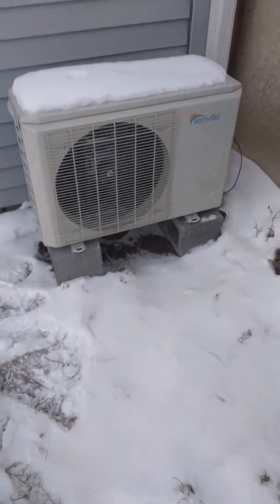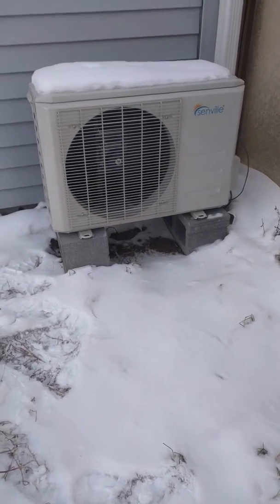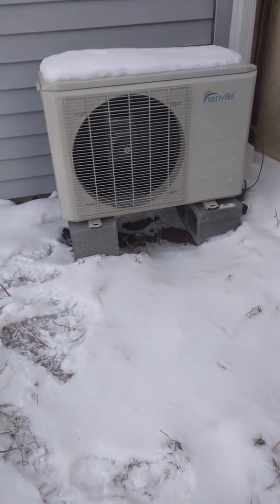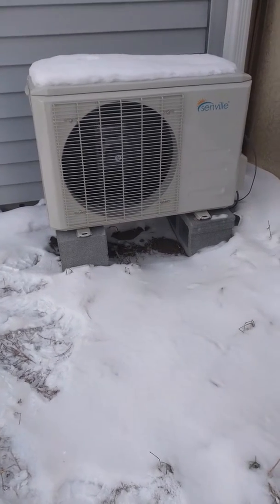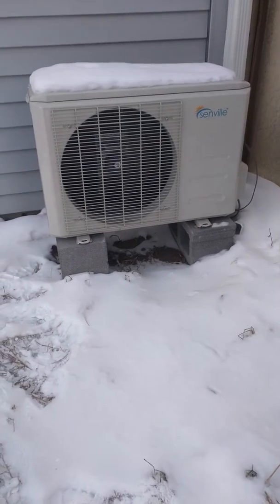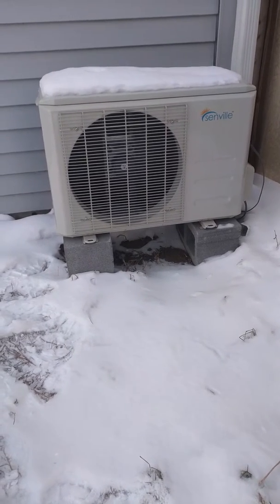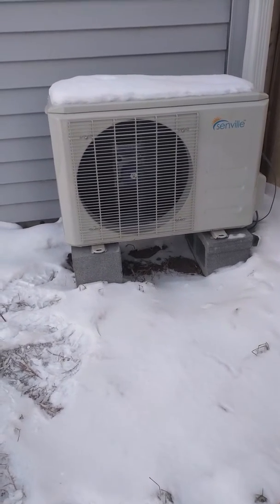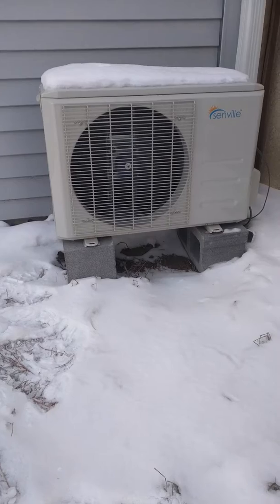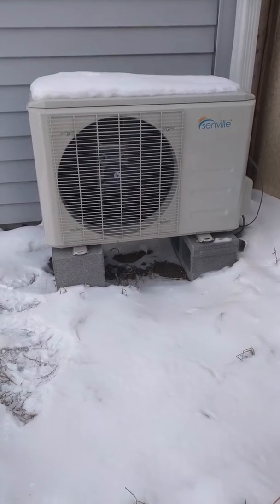I just wanted to do another video on the Senville HFZ units — this is the 12,000 BTU. I took a few videos this spring, and it's December again right now. It's two degrees outside. The unit is running at full capacity, which my power monitor shows around 1800 to 1900 watts. It seems like it will peak at two kilowatts but holds around 1800, then comes back down.